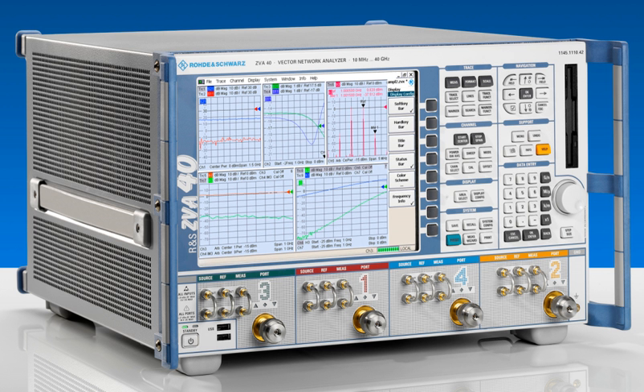The simplest calibration that can be performed on a network analyzer is a transmission measurement. This gives no phase information, and so gives similar data to a scalar network analyzer. The simplest calibration that can be performed on a network analyzer, whilst providing phase information, is a one-port calibration, S11 or S22, but not both. This accounts for the three systematic errors which appear in one-port reflectivity measurements. Directivity: error resulting from the portion of the source signal that never reaches the DUT. Source match: errors resulting from multiple internal reflections between the source and the DUT.